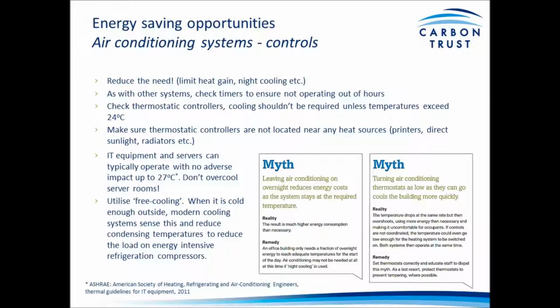Please do consider these two myths that we've provided here. One is that if you leave air conditioning systems on overnight, they don't have to bring up or have a heavy load of temperature change in the morning. This will save energy. This is not true. You're much better in a vast majority of cases to be running your system when you are in the office, not overnight. You have set back temperatures, certainly, but certainly don't run the system as a fully occupied office or any building during the night.